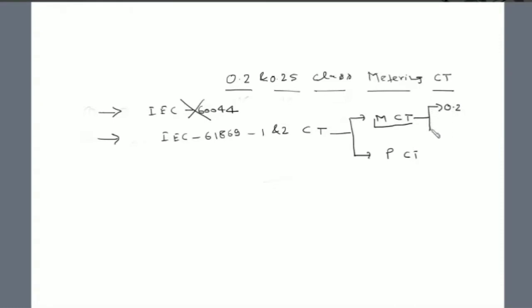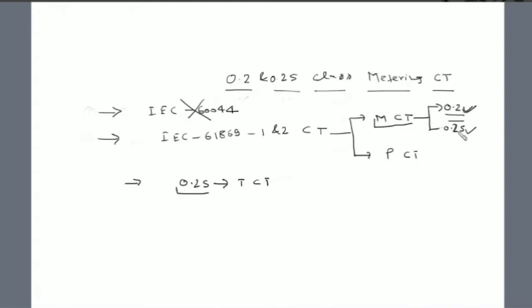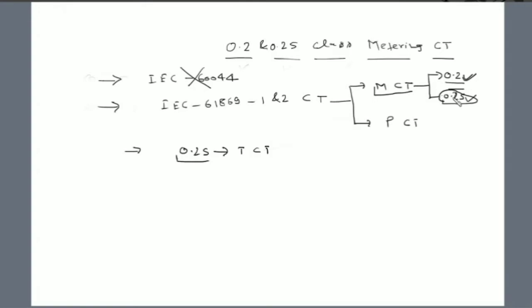In substations we mostly use 0.2 or 0.2S class CT. The difference is where we will use 0.2 and where we will use 0.2S. The 0.2S class CT is used mostly for tariff metering applications — that is, for revenue metering purpose, 0.2S class CT is preferred over 0.2 class CT.